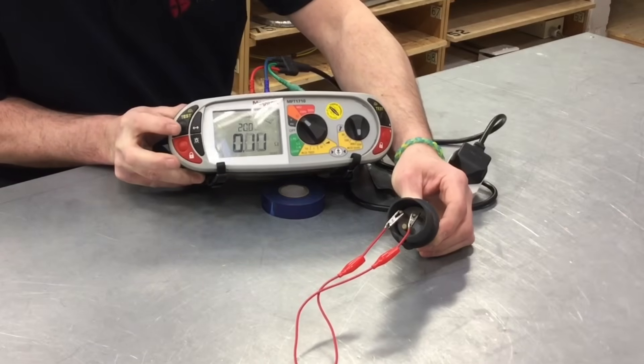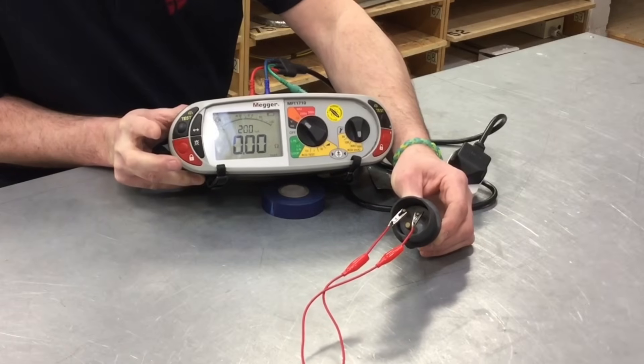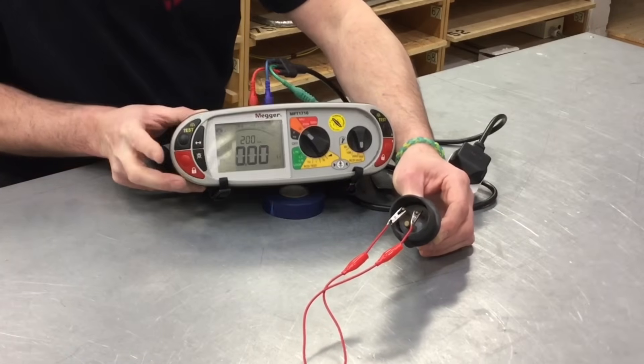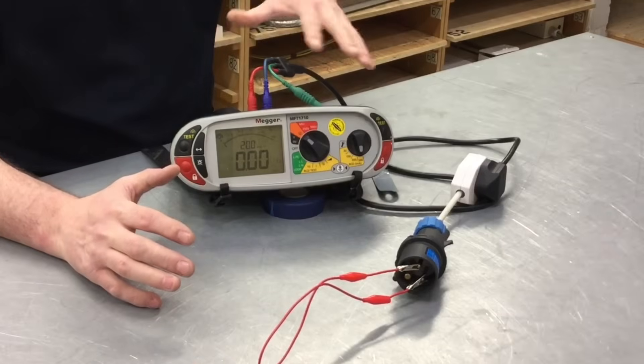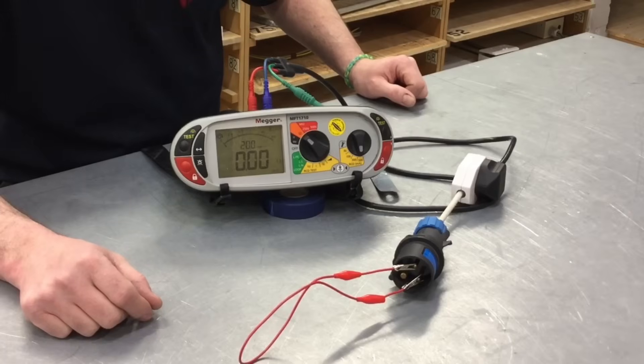We press the test button once - we get a reading - press it again. As long as it isn't flashing zero, we are at zero. So we've removed both the resistance of our plug-in lead, our modified adapter and our link. Therefore we're ready to test between line and neutral as part of polarity.